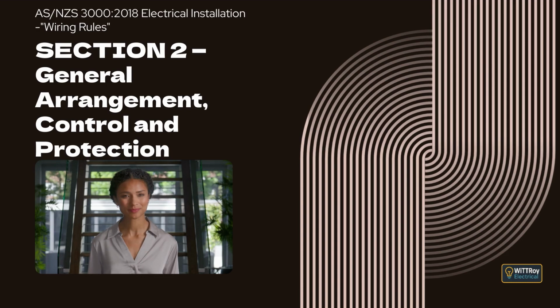If a switchboard needs to disconnect all live conductors of a circuit, the device must be designed so the neutral cannot be disconnected or reconnected without the actives being disconnected first and reconnected last. This protects people from unsafe neutral conditions. The safe sequence is simple: disconnect the actives first, then the neutrals. Reconnect the neutrals first, then the actives.